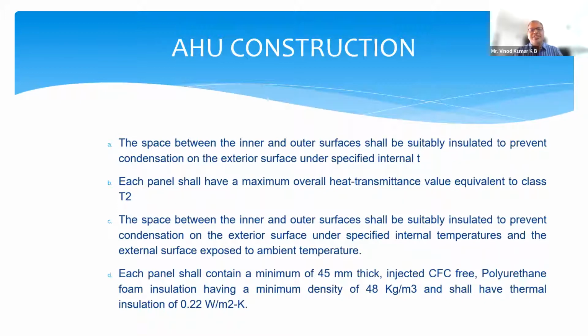Then coming to T2. T2 is another classification. What is this classification? This classification is basically to make sure that the heat transmittance from the outside of the AHU to the inside is the minimum. Okay. So the classification of your AHU has to follow that of T2. This happens when you have the correct kind of casing, which I just said before, the inner casing, the outer casing, and the insulation in the middle. You look at the last line. Between these two casings, you will put the insulation.